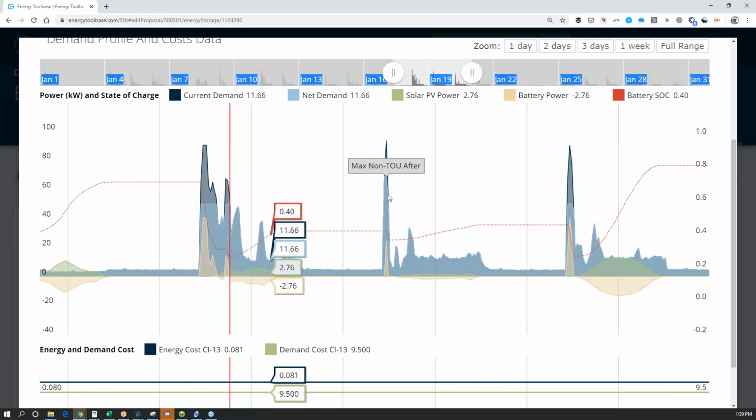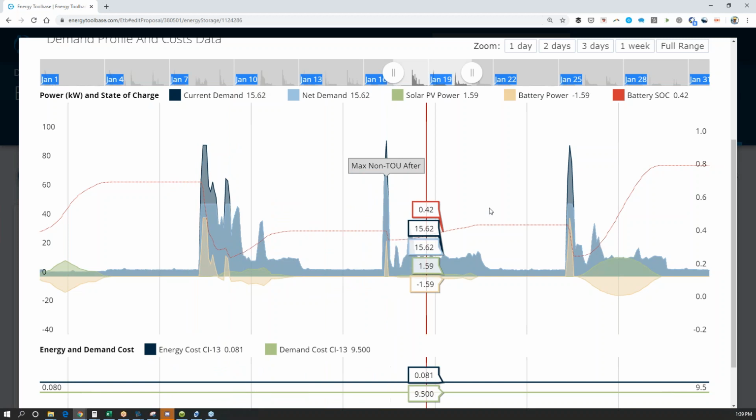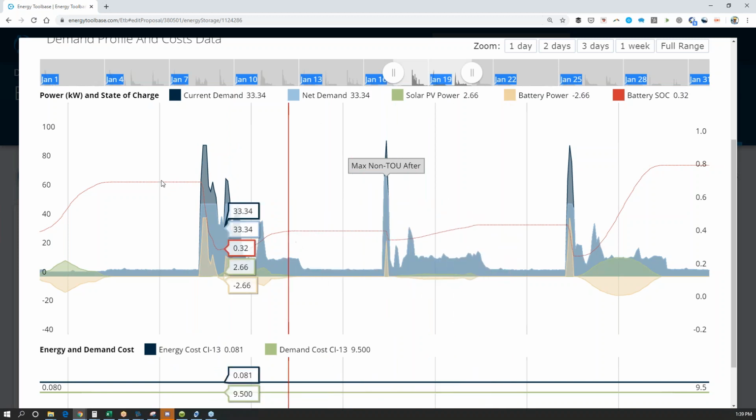And so now we have the day where we have our maximum bill after the project. So why is it being pushed further on into the month? Well, previously we've incurred a demand charge of this amount, and so now the battery says, okay, I'm only going to try and level the demand if we get above that amount. Otherwise, I might turn on a little bit to play some preventative games, but I'm not really going to run at other times when the demand isn't getting up to that point.